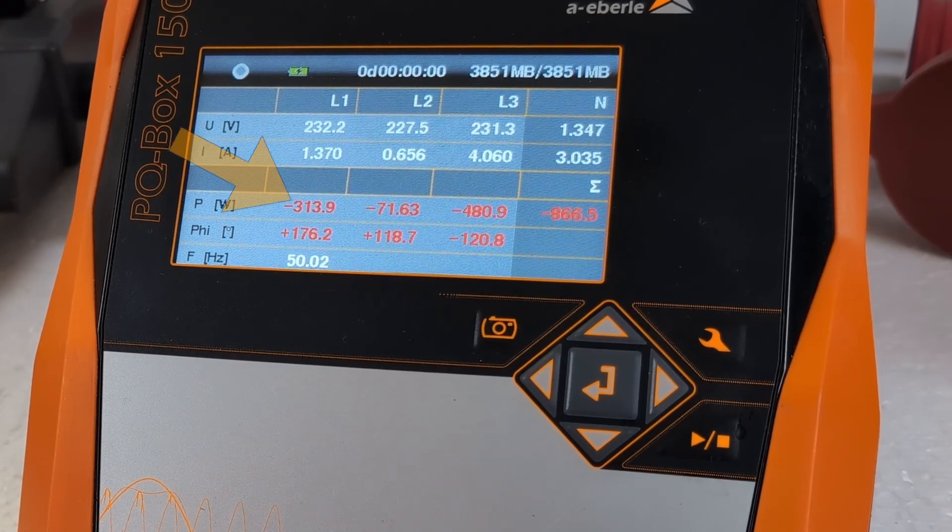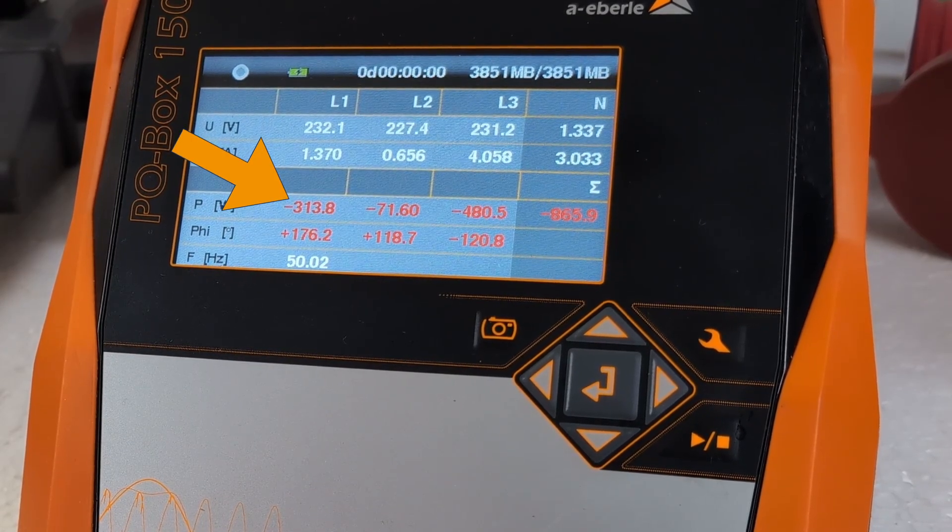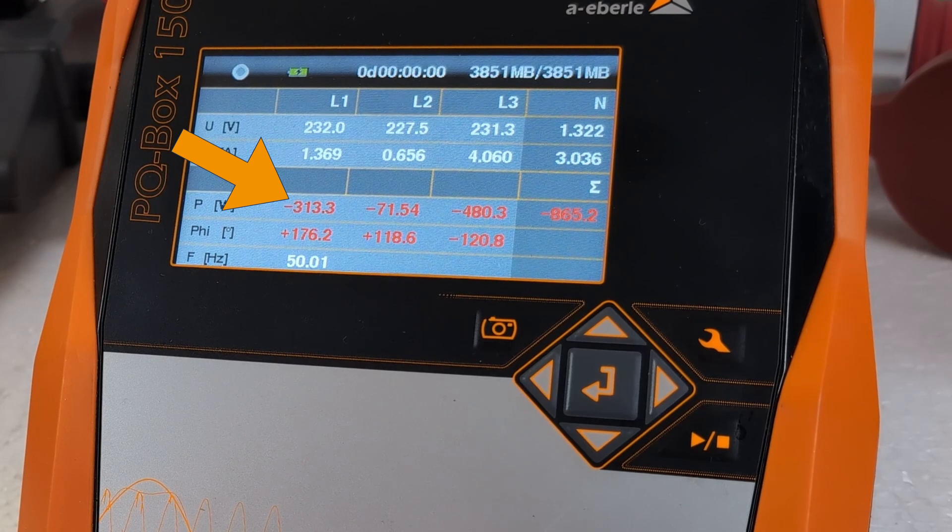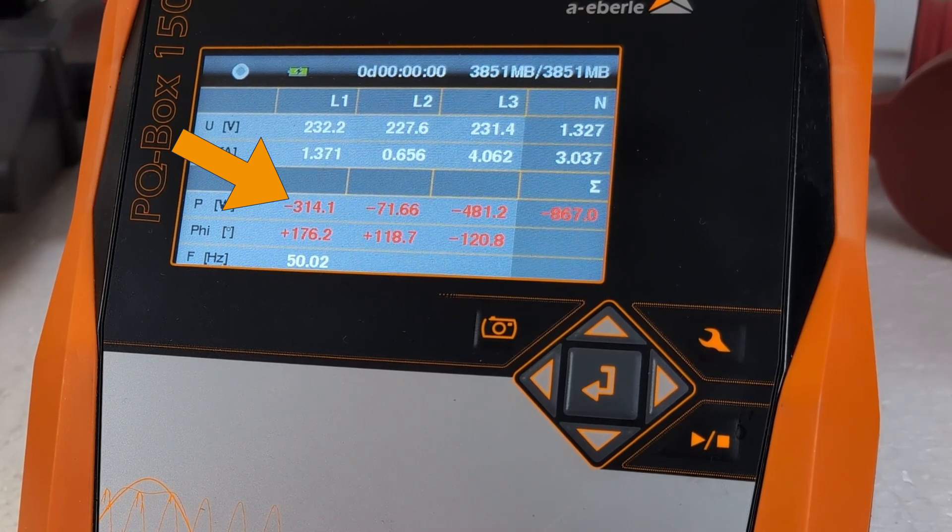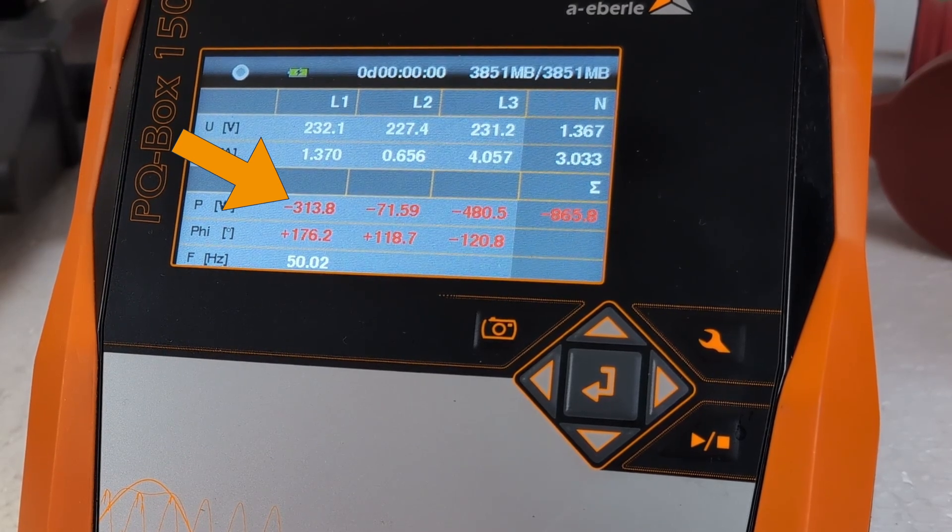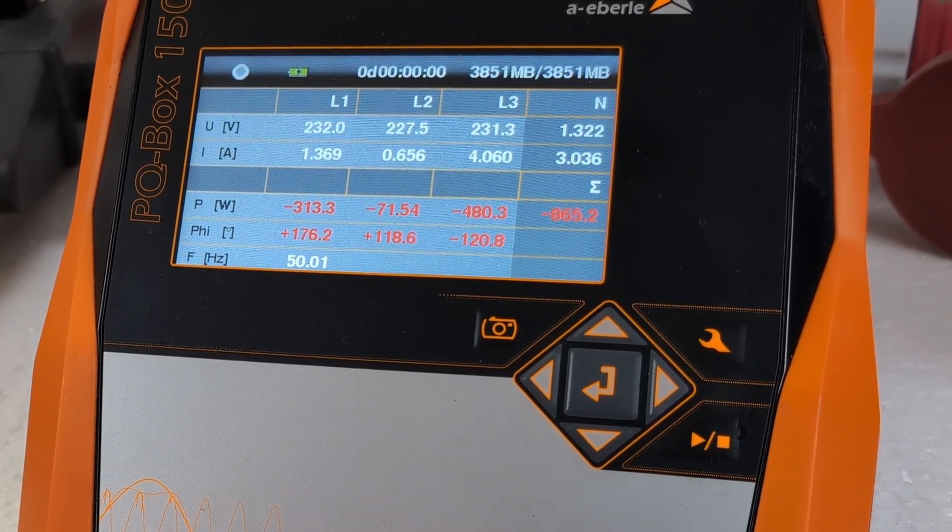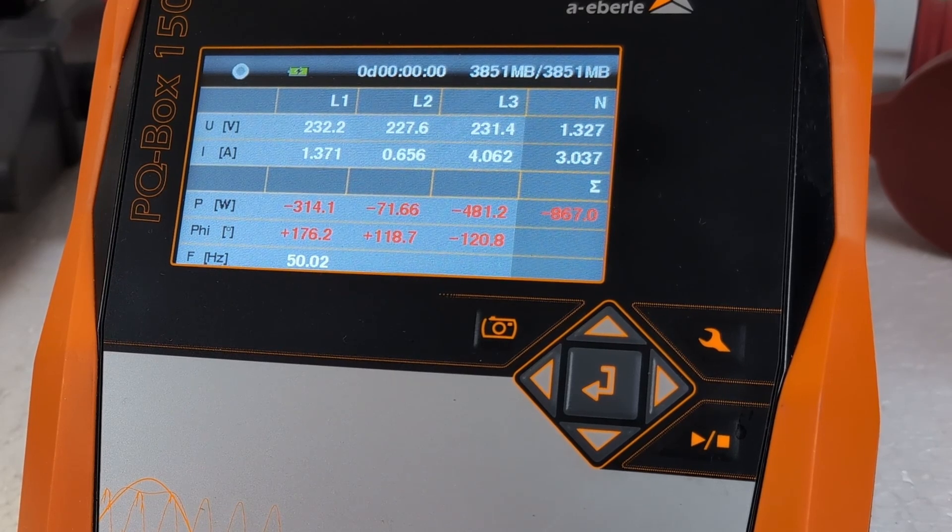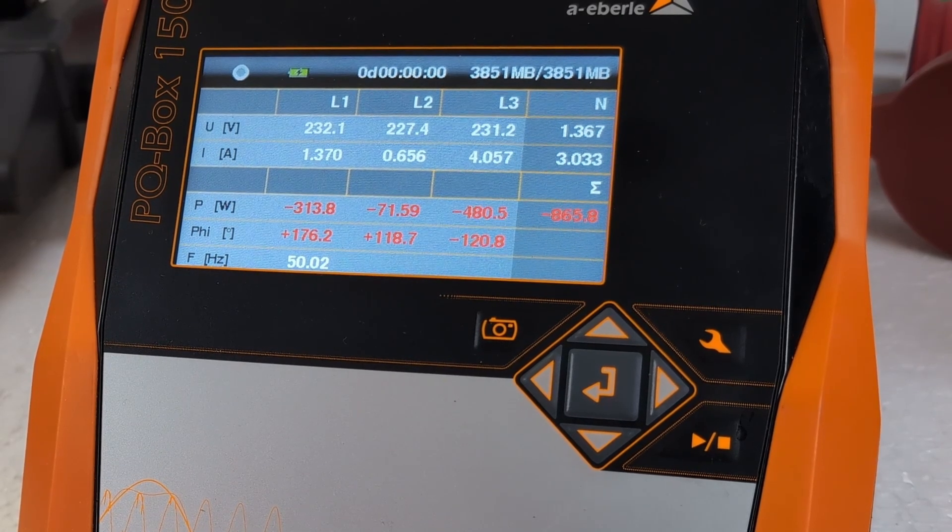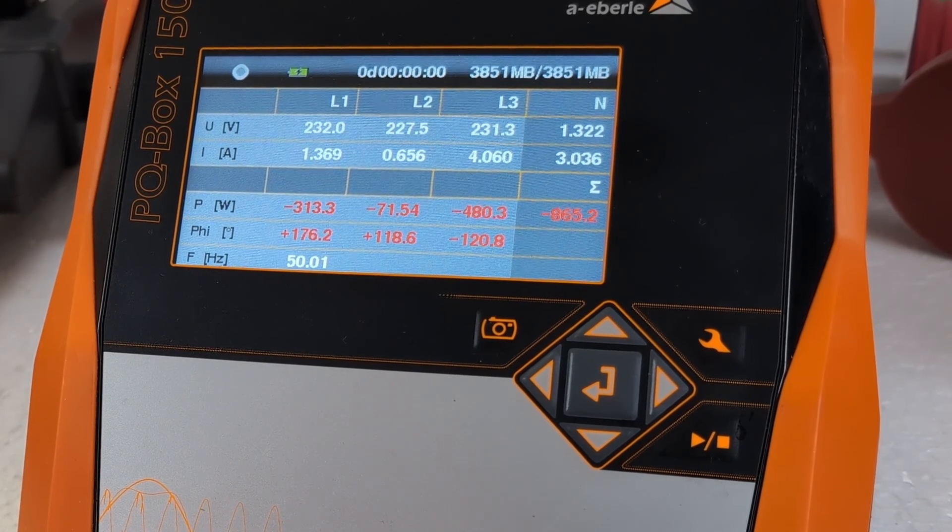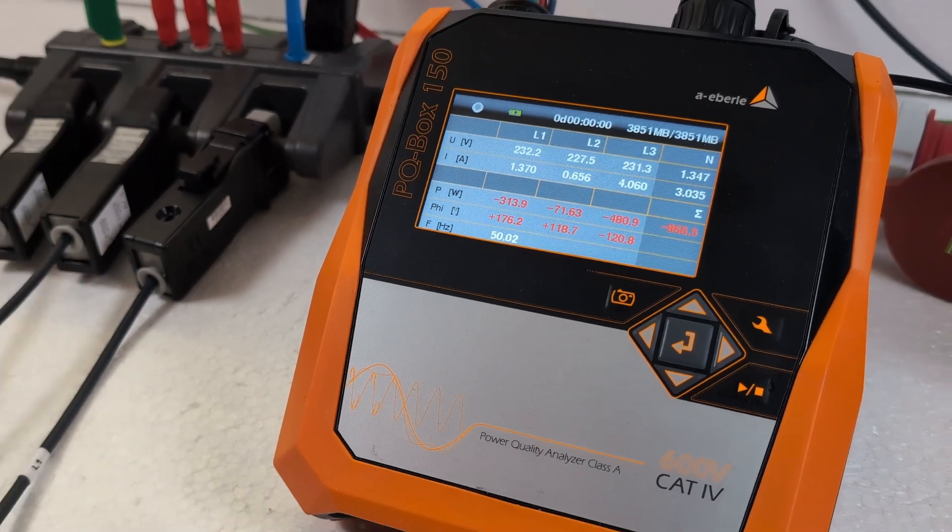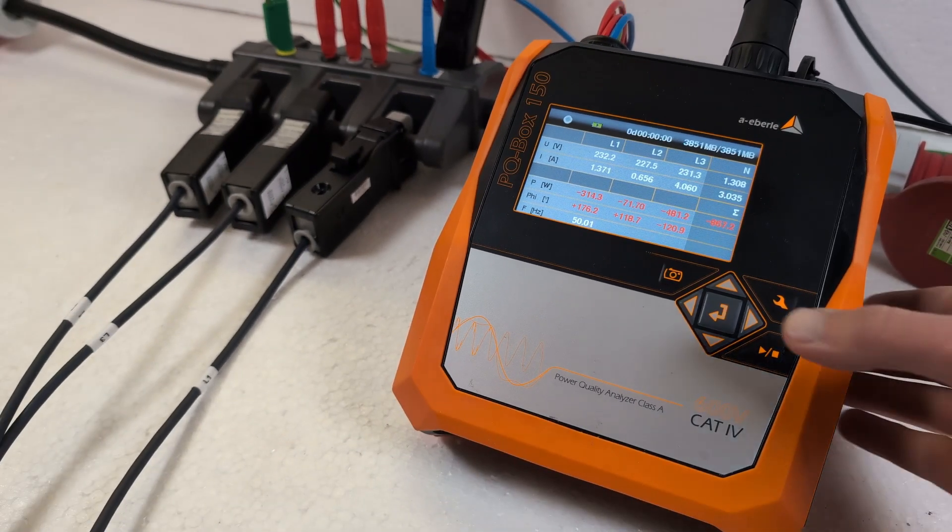Red values for the active power P immediately show me that something may be wrong here. If I measure a classic load, which is the case here, all three values should have a positive sign.